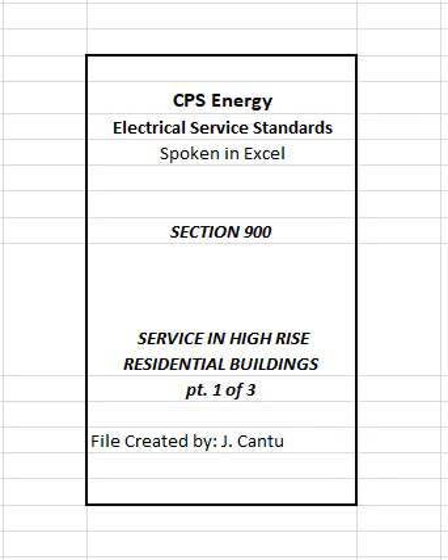902 Feeder risers supplying meter rooms. Each feeder riser raceway shall include all of the ungrounded, phase, conductors plus the neutral conductor, and the conductors shall extend into the disconnecting device ahead of grouped meters in each meter room. A. Feeder conductors. Conductors shall be sized and supported as specified by the NEC. Customer shall be responsible for submitting calculations to the CPS Energy Customer Service Representative that verifies the voltage drop at metering equipment does not exceed 2.5%. Refer to Section 300.